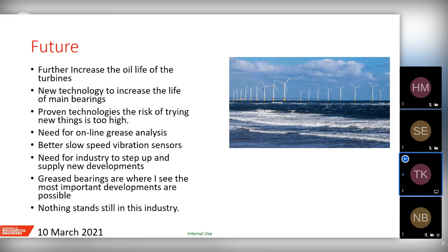There are sites that have been out there and had every gearbox changed by massive jack-up once a year in the first few years, till they got to the bottom of a fault, which was just small material defects in bearings. But that cost the supplier at least millions, tens if not hundreds of millions. It virtually bankrupted one of the biggest wind turbine manufacturers, having issues like that.